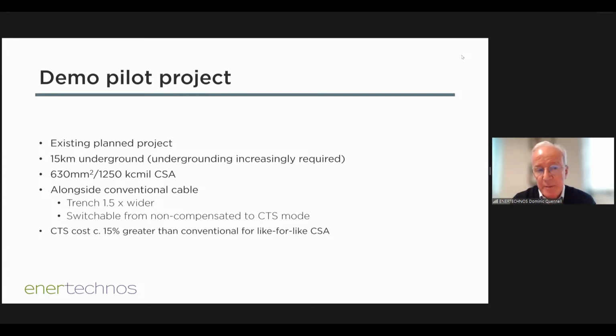Size is probably 630 millimeters squared, or 1250 kcmil. In terms of cost, the trench will be a little wider, since you'll end up with two cables side by side if you run one alongside a conventional cable. The actual cable cost is about 15% greater than a like-for-like conventional cross-sectional area.